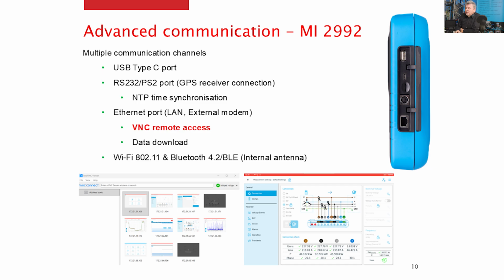Then you have the RS-232 PS2 port, which is used for the GPS receiver connection. In this case, time on the instrument will be synchronized up to 1 millisecond resolution, and the instrument will also detect its position, which can later be presented with Google Maps in the NP-Vision software. Internally, we also have NTP time synchronization. So when you connect the instrument to Ethernet, it will simply synchronize automatically. Otherwise, you need to synchronize it manually.